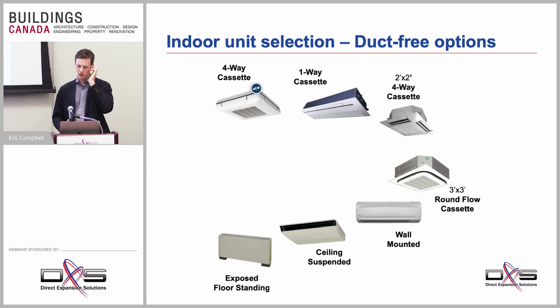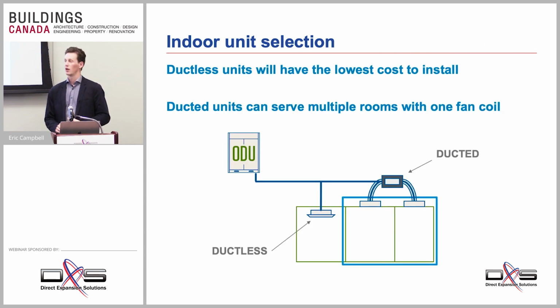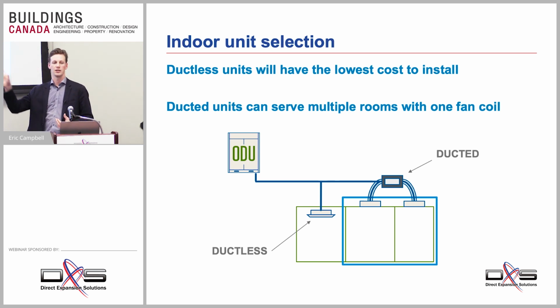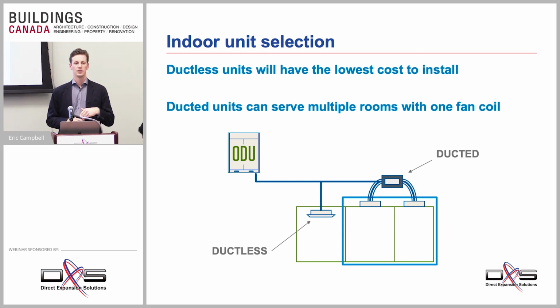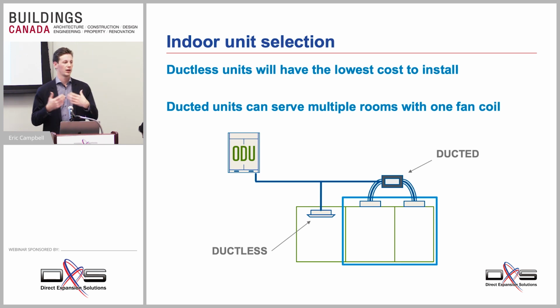So typically, something like a ductless unit is going to have the lowest cost install because you're just hanging a single unit on the wall. On the other side, you've got ducted units, which are going to require drywall work and hanging work, so you've got increased cost there. On the flip side of that, a ducted unit could serve multiple spaces. So you could put one ducted unit in a space and serve the living room and the bedroom, or living room and two bedrooms, or three bedrooms. It depends on the size of the system and how much you want to route that ductwork.